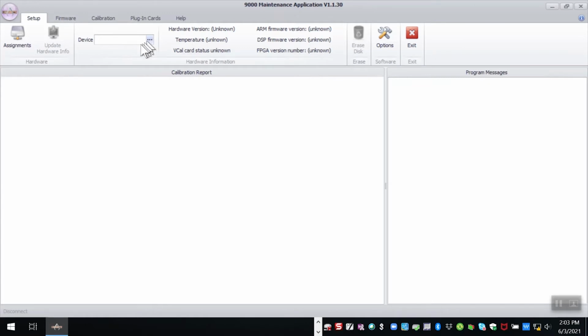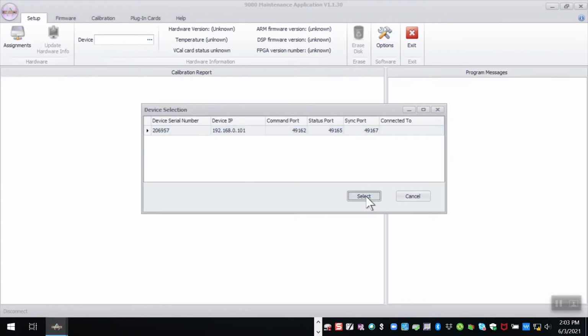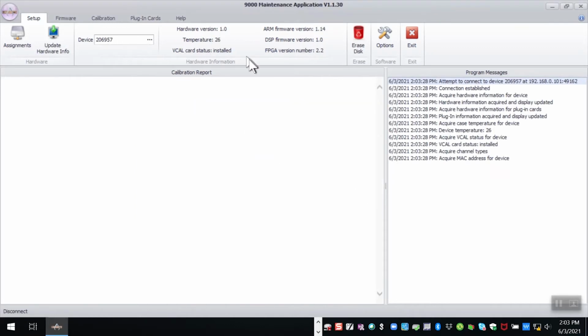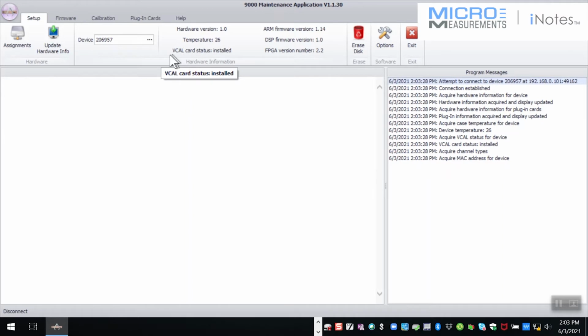If I were to select that device, if I've got multiple scanners, I'd have some to choose from. But by selecting this particular device, it gives me a report that gives me a status on several things, including the temperature within the scanner and whether or not I have a voltage calibration card installed. And I do, a VCAL card. The VCAL card is an NIST traceable standard on resistance, and that VCAL card is something that I can use to do a system calibration. It'll check the voltages, inject voltages in each of the channels and check the measured ones to make sure everything's appropriate, potentially adjust any gain amplifiers within it, and it'll give you a report back as to whether or not everything's copacetic.